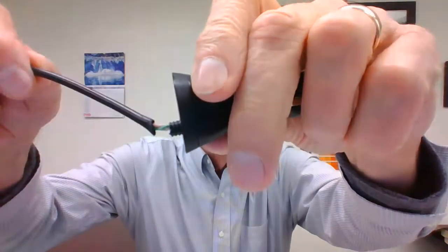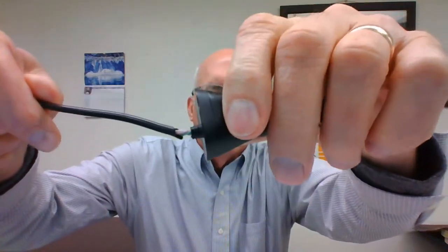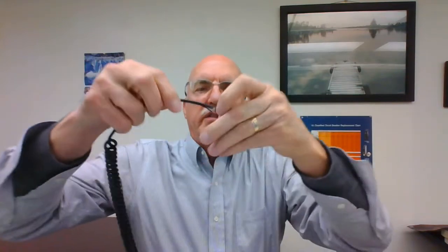Well, arcs begin as a result of tool cord or extension cord or lamp cord that's been physically damaged and stressed to the point where the insulation or the sheathing has broken down. An extension cord constantly stressed at the same point will eventually develop a break in the insulation. I have one here that I could show you. At this end of the cord, for example, you can see where the sheathing is already broken, and then the conductors in there are next. At the other end of this cord, it already has frayed enough, and you can see the copper conductors already coming out of the inside insulation. So that's the type of thing that happens to these stressed cords.